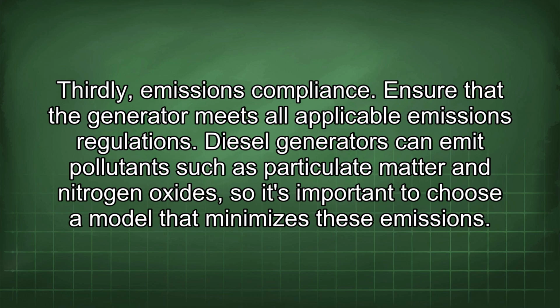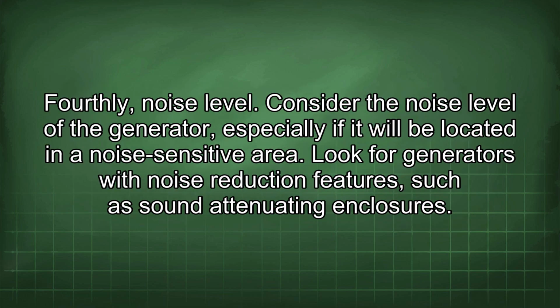Thirdly, emissions compliance. Ensure that the generator meets all applicable emissions regulations. Diesel generators can emit pollutants such as particulate matter and nitrogen oxides, so it's important to choose a model that minimizes these emissions. Fourthly, noise level. Consider the noise level of the generator, especially if it will be located in a noise-sensitive area. Look for generators with noise reduction features, such as sound attenuating enclosures.